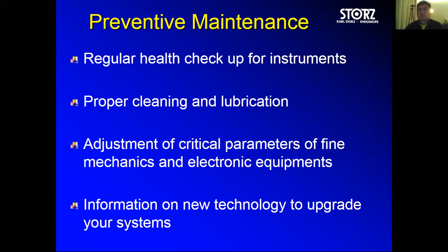If you have one single instrument and it's going to break and you don't have a standby, you are really stuck. So lubrication is important, and it should be stored in a dry area. I see the sisters take a cloth and clean the instrument with the same wet cloth. They should have a hair dryer, which they use after the bath. The instrument should be totally dried, dismantled, lubricated, and sent. Once it is on the sterile trolley, it cannot be lubricated. It does not follow an aseptic technique.